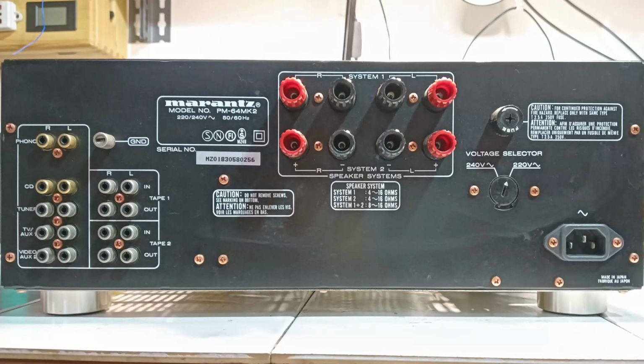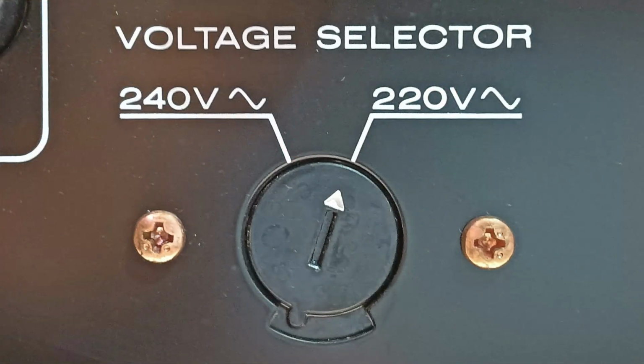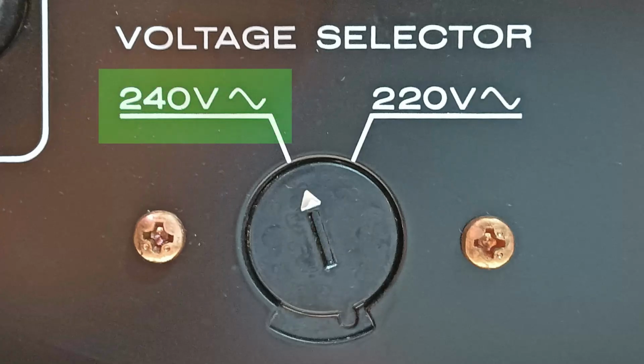The cabinet back panel has an input voltage selector that allows choosing between 220 and 240 volts. In Europe, the mains voltage has been harmonized to 230 volts, and in this case, it is advisable to select 240 volts.